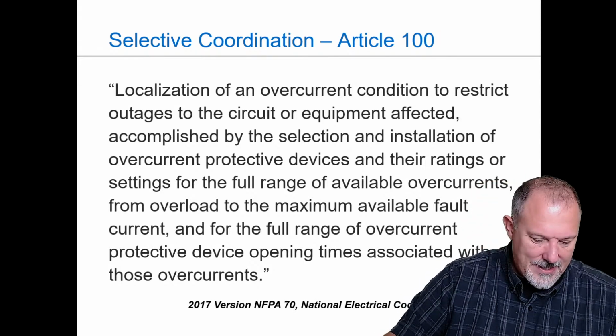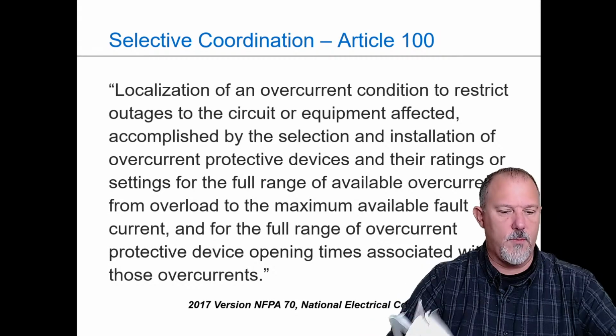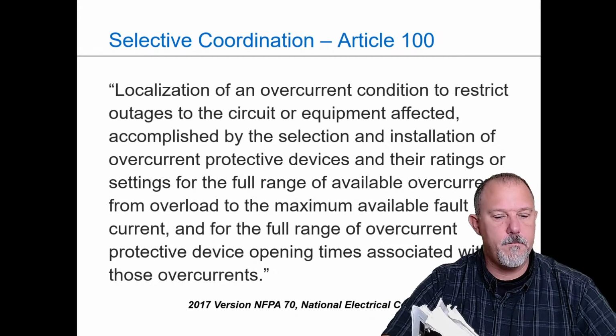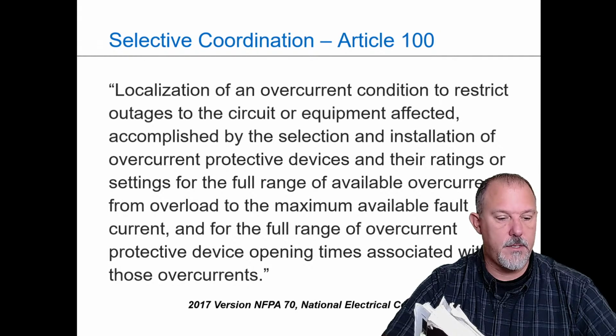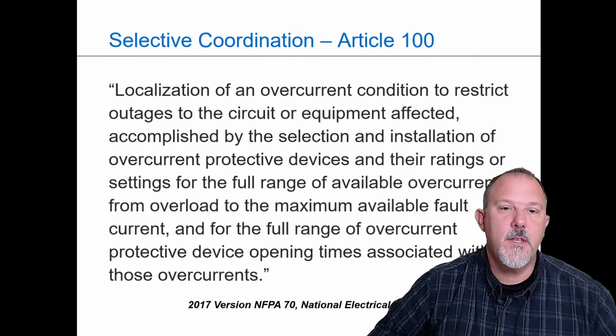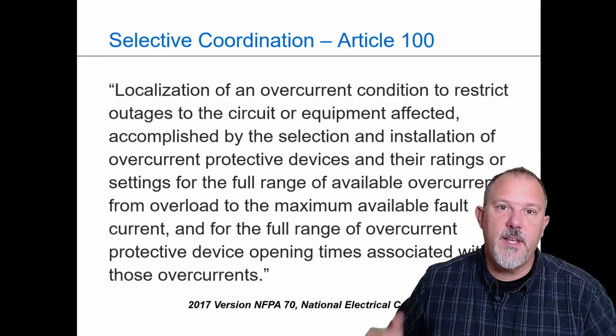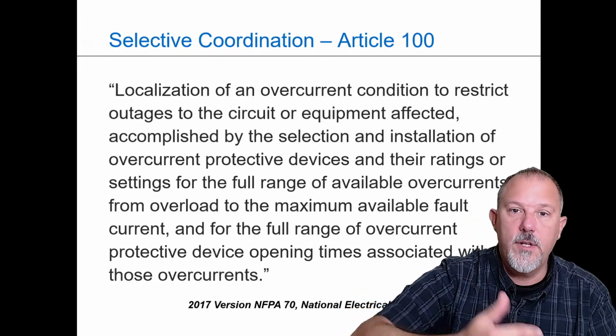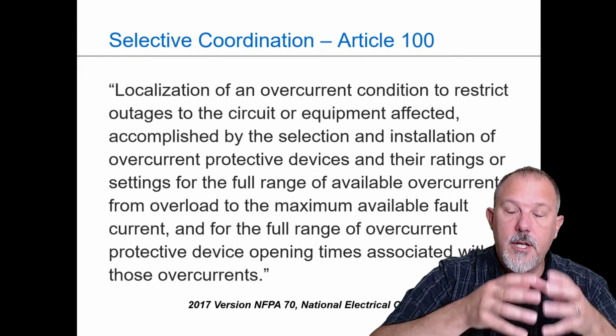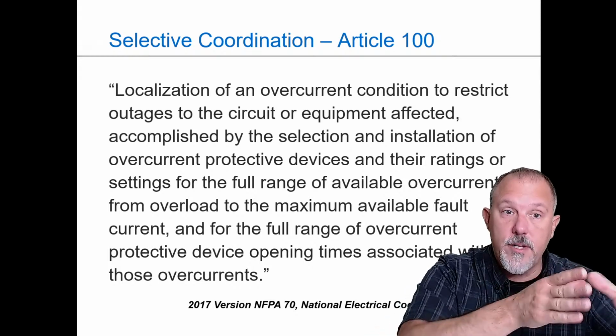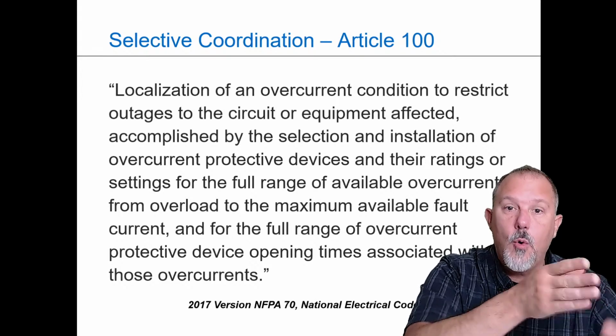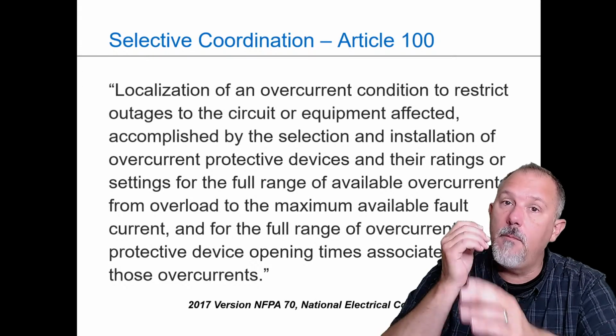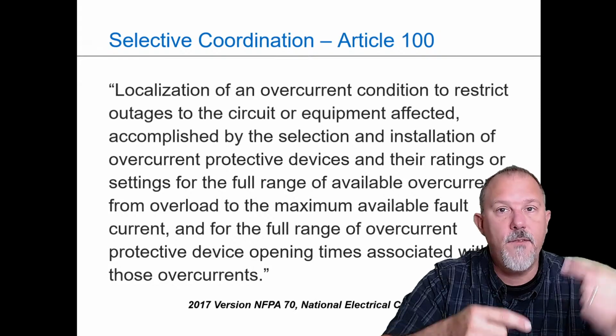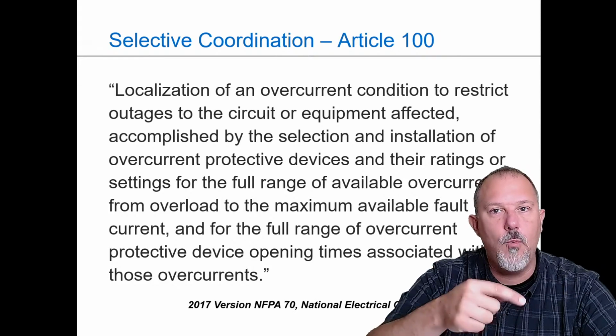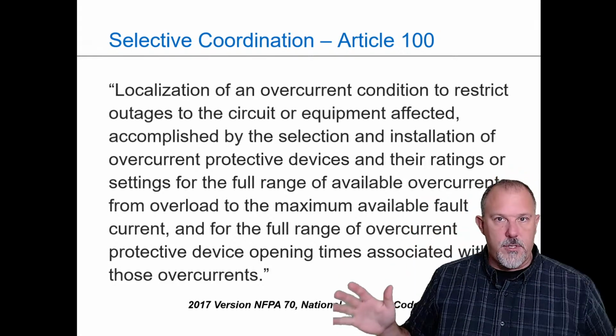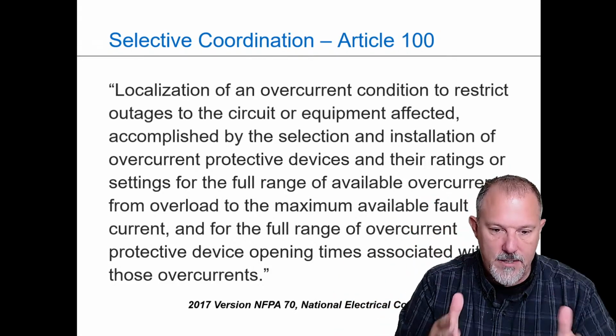And that's got to be the longest sentence. It's got to be more than one sentence. So, man, it looks like it is one big sentence. Okay, so up to the very first comma, what does that tell me? That tells me if I have a fault, I want to localize the overcurrent condition and restrict my outage to the circuit or the equipment. So if I have a motor that has a short circuit into it, whatever is directly feeding that motor, I want that motor to be taken out, nothing else. So that is the concept.